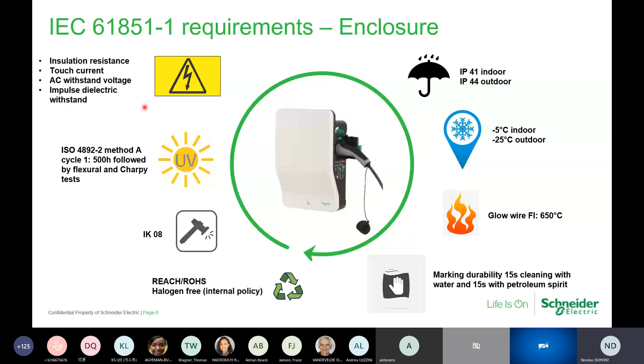Another key requirement is the IK 8. So it's a minimum, but all of our products are tested for IK 10. And for me, the last main requirement is the UV resistance. So there is a UV test method in the standard. And we have also a requirement for electrical safety. So with all of that, we choose a PC UV stabilized. It's a cost-effective technical solution. So as you can see, it's a pretty common material, and it's not so difficult to find the good material for this standard.